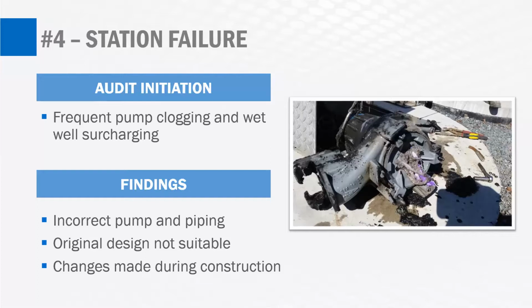We found that the original design was not suitable. One of the issues that this station was facing is the wastewater stream coming to the station was primarily from schools, and there was a lot of debris, things like mop heads, coming down the gravity sewer line that the station was not suitable to handle. And there were significant changes made during construction that we were able to find through documentation. There wasn't a lot of reason behind it, and it doesn't seem like there was a lot of analysis behind these changes to deviate from the original design.